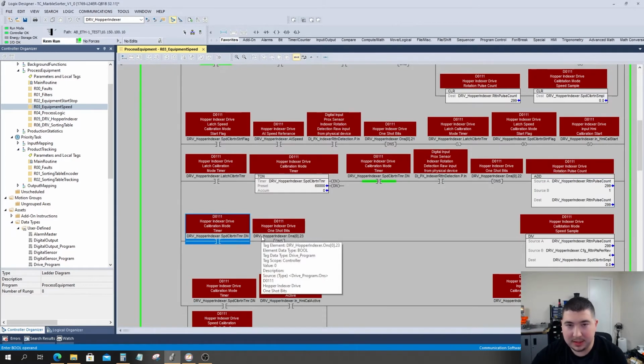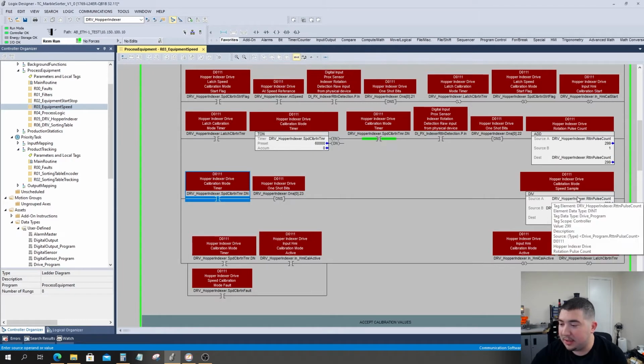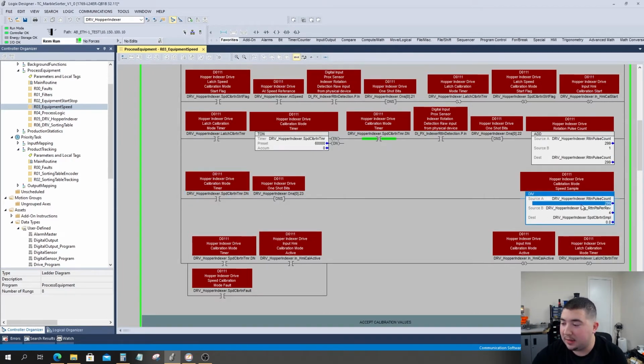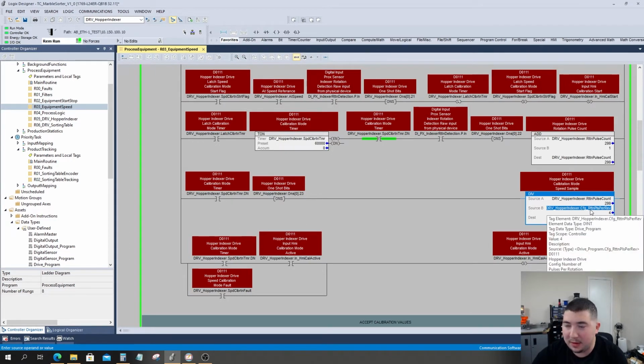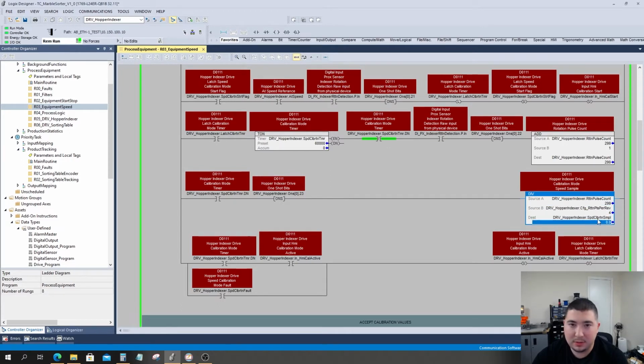When the counter has completed its operation, we can then determine how many pulses there were per revolution and check that against our final speed, or our actual speed measurement. Since we have 4 metal bits on that rotary axis in this particular example, I have this little divide operation. Basically this is saying how many times we're going to see this flag that we're looking for in a given rotation of this axis. In this case there's 4, so I say 4. That means whatever number of pulses we see, we divide that by 4, and that gives us our total number of rotations per minute.